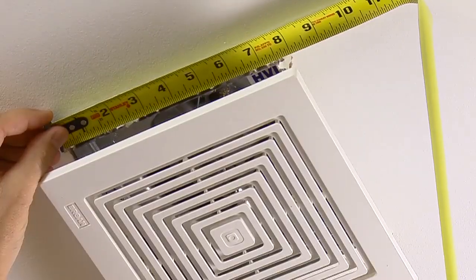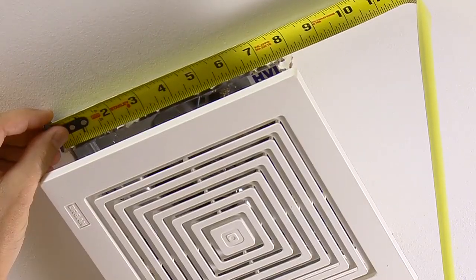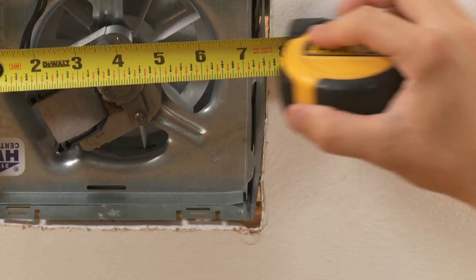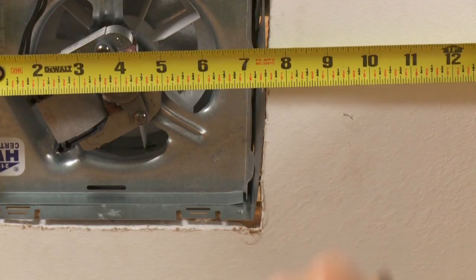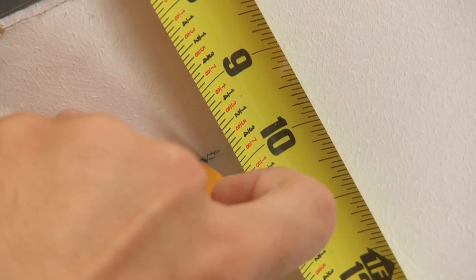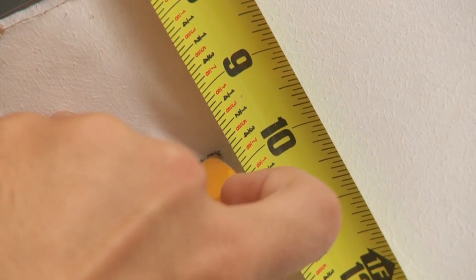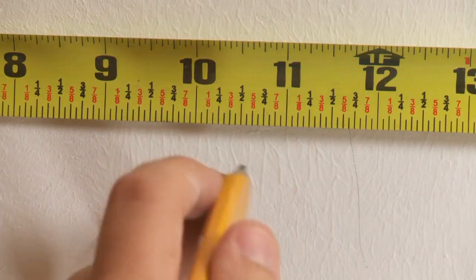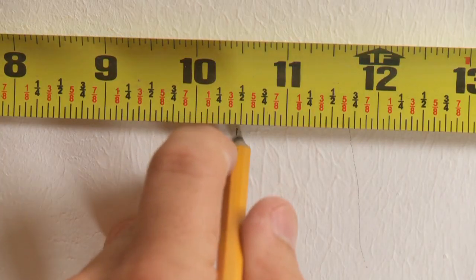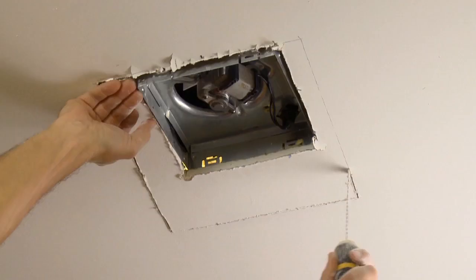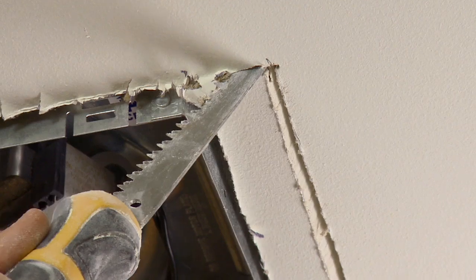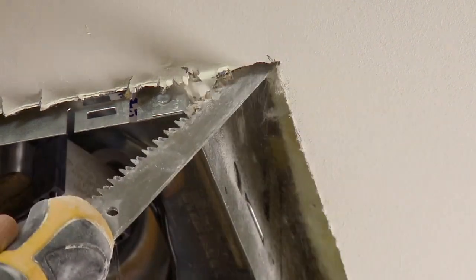In a retrofit installation, first determine if you must expand the hole. If necessary, enlarge the ceiling opening to 9 ¾ inches parallel to the joist by 10 ½ inches perpendicular to the joist. Be sure not to cut through any ducting or wiring.